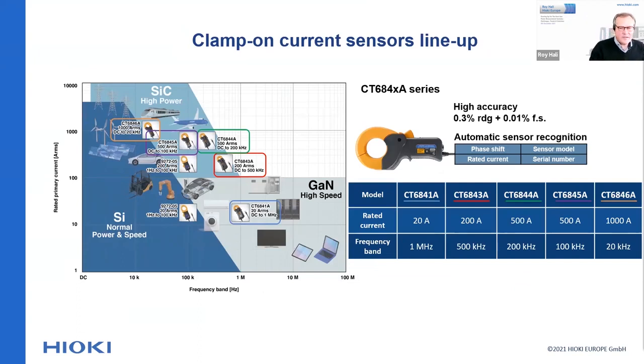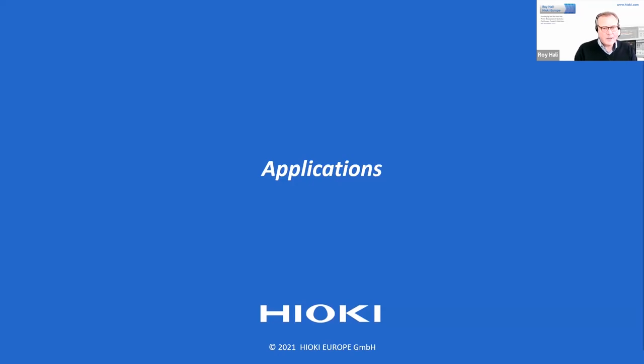Although you might think that clamp-on sensors are not the right fit to be used in combination with this high-spec power analyzer, we think that the clamp-on sensors in the CT684xA series are worthwhile to consider. Their basic accuracy is 0.3%, and the wide operating temperature of -40 to +85 degrees Celsius makes them popular, for instance, for WLTP tests of vehicles with an electrical drivetrain. Also, for the evaluation of solar power conditioners where the bandwidth is not any issue, the clamp-on current sensors can be considered. Let's take a look at the applications where the PW8001 can be used.